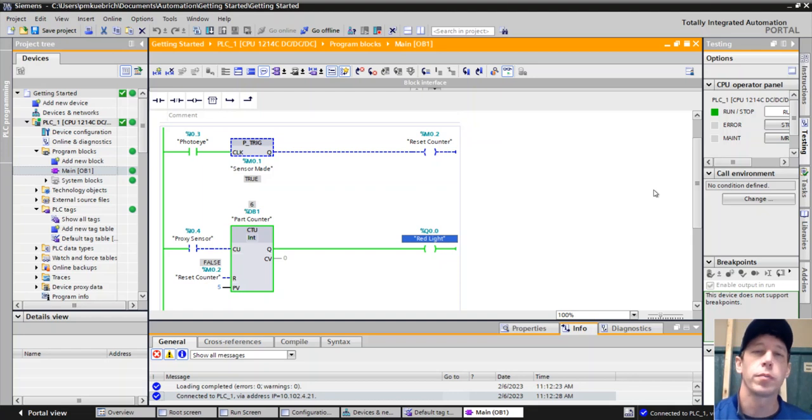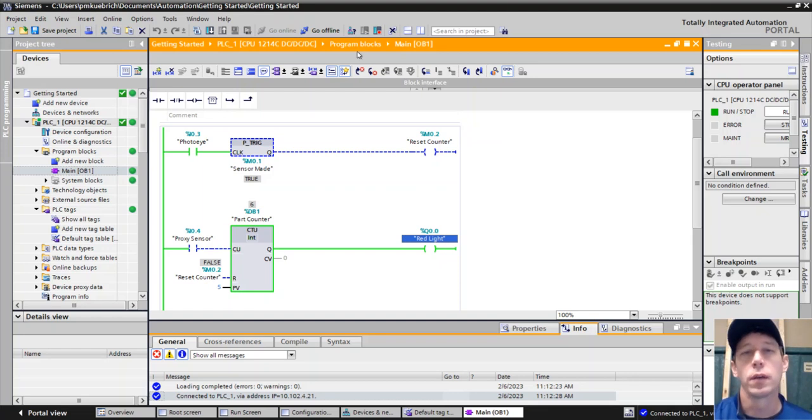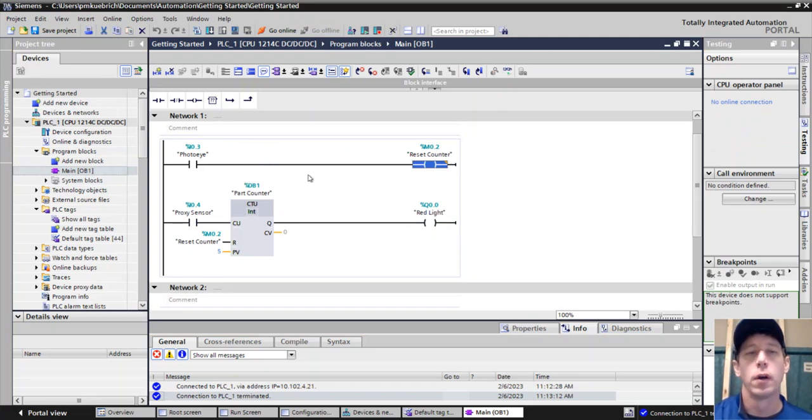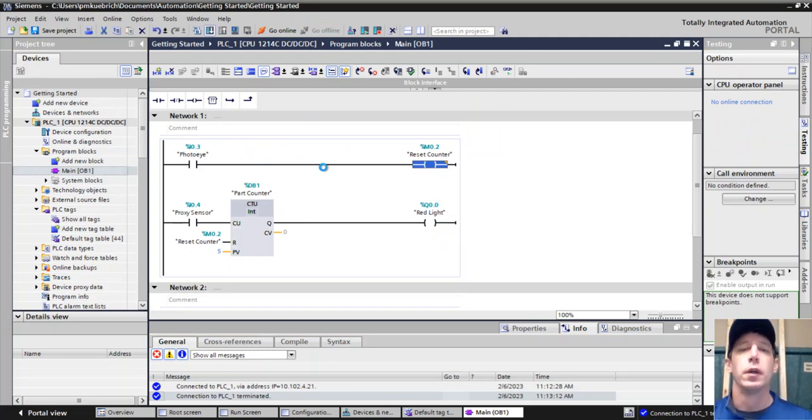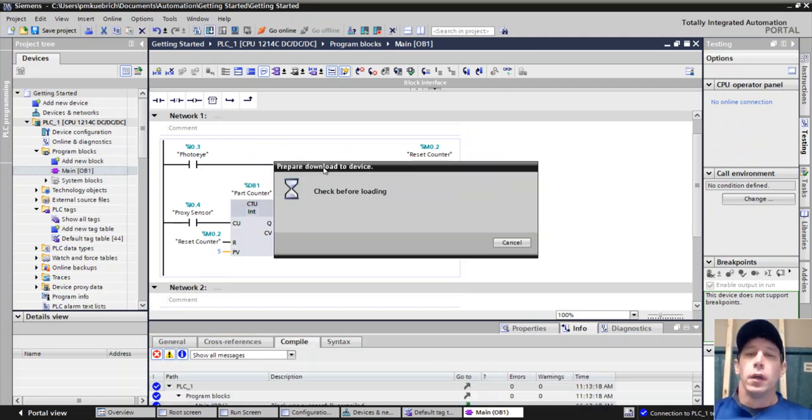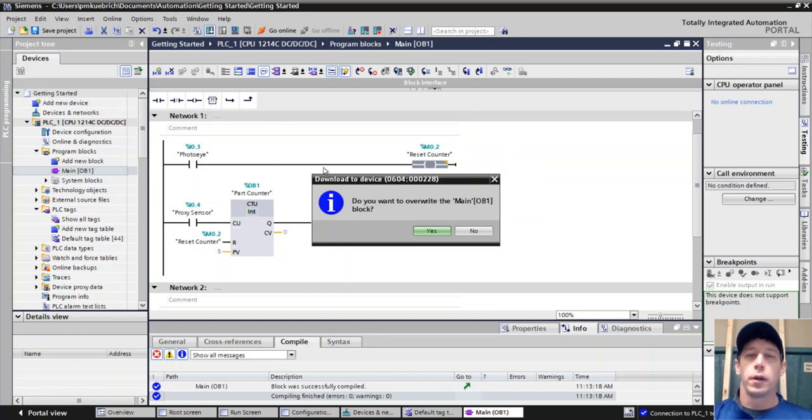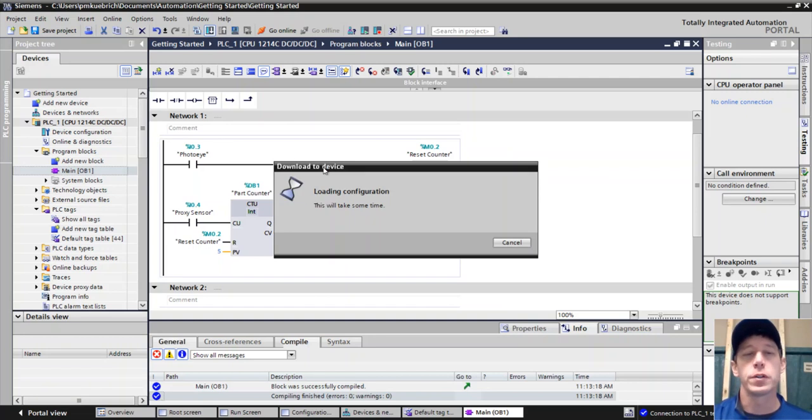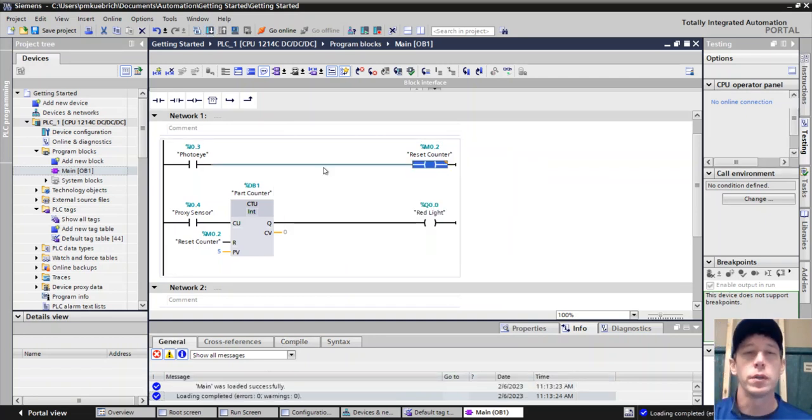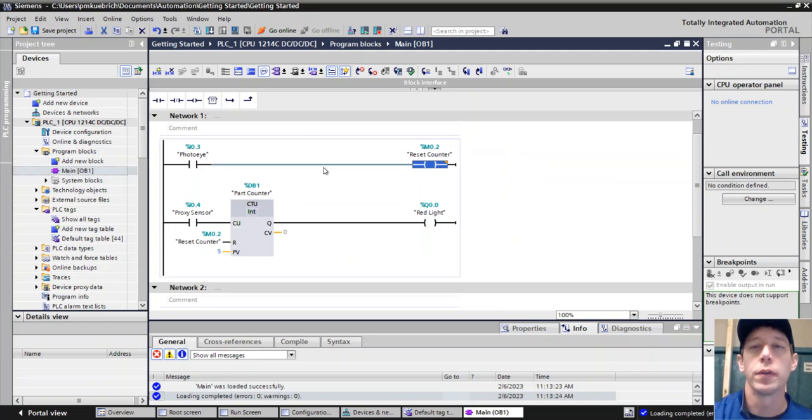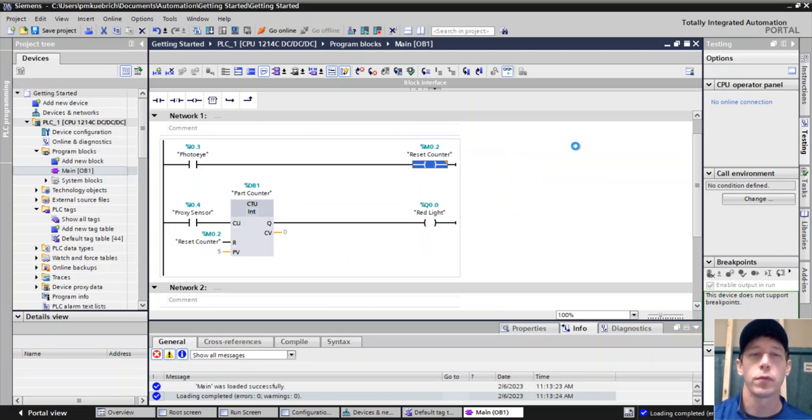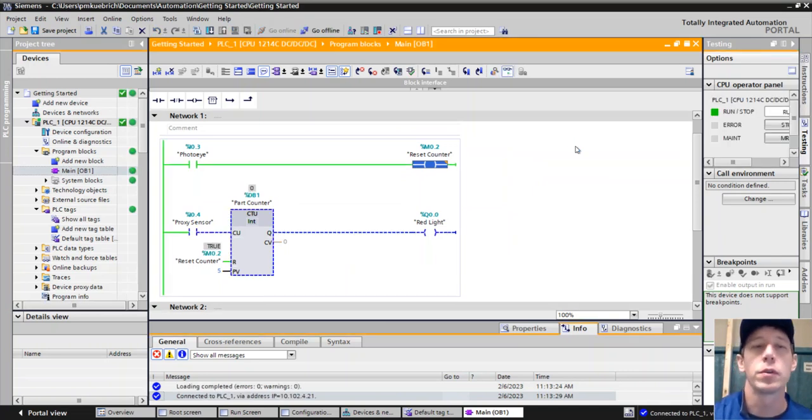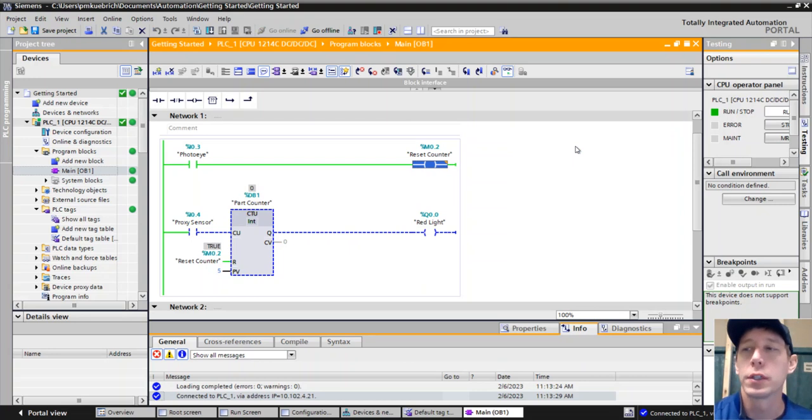Now, a little bit more explanation as to why we would need this. Let's see what happens if we don't have our one-shot in there. You can understand, if we don't have our one-shot in there, the counter will always be resetting anytime the sensor is made, anytime you have something in front of the photo eye. We're going to constantly be resetting the counter, which means it's not going to actually be counting.